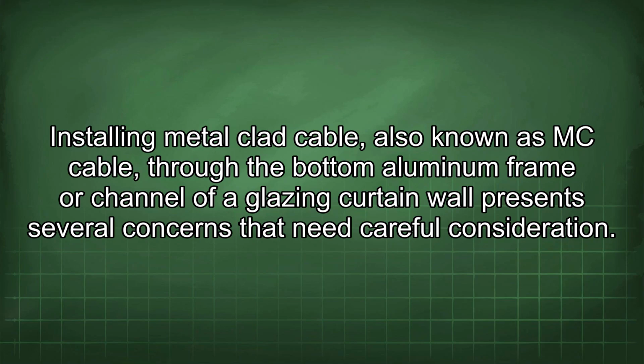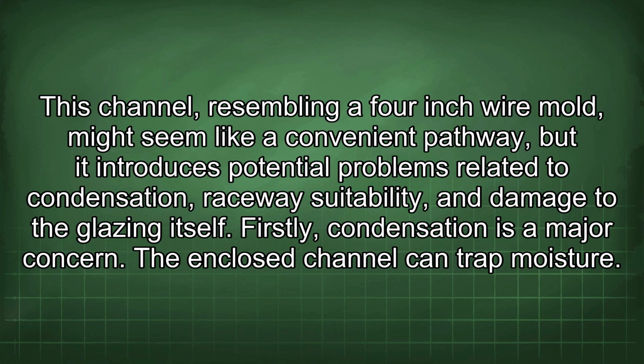Installing metal-clad cable, also known as MC cable, through the bottom aluminum frame or channel of a glazing curtain wall presents several concerns that need careful consideration. This channel, resembling a 4-inch wire mold, might seem like a convenient pathway, but it introduces potential problems related to condensation, raceway suitability, and damage to the glazing itself.